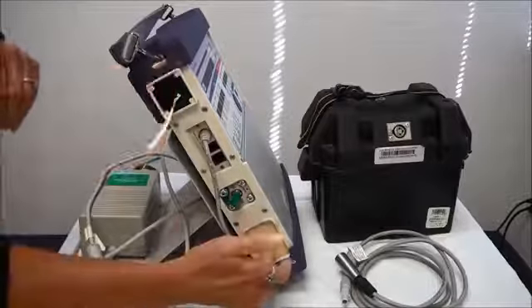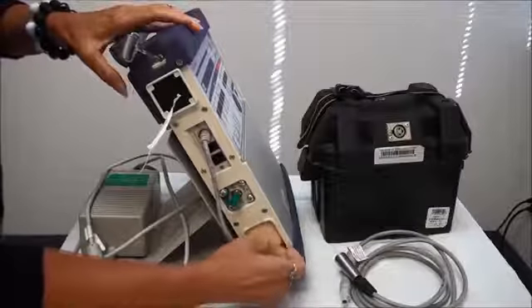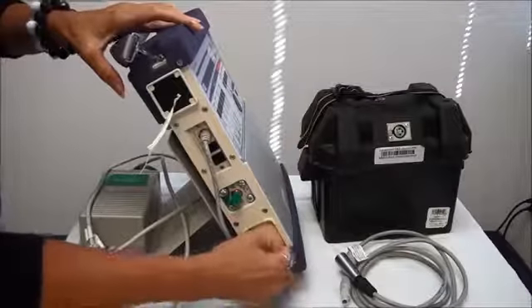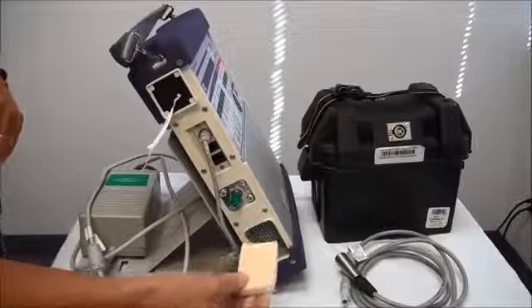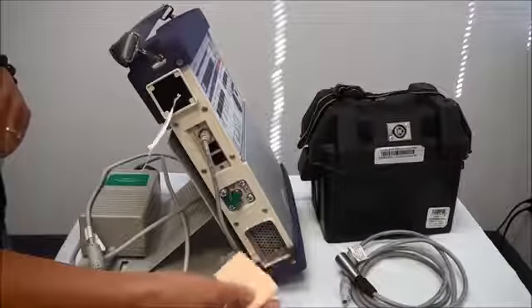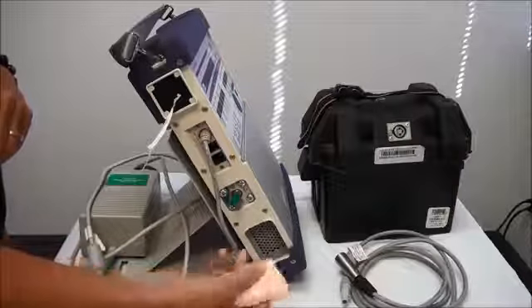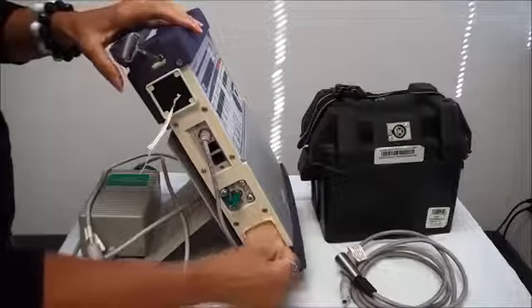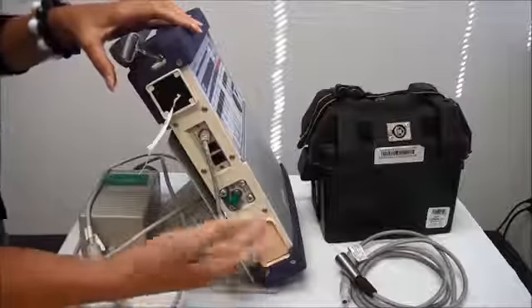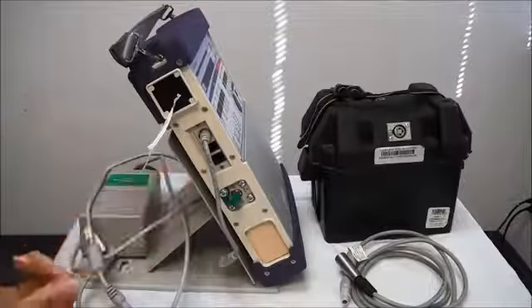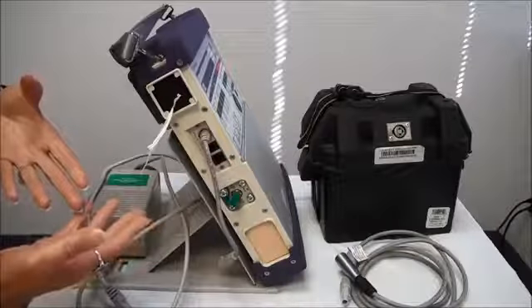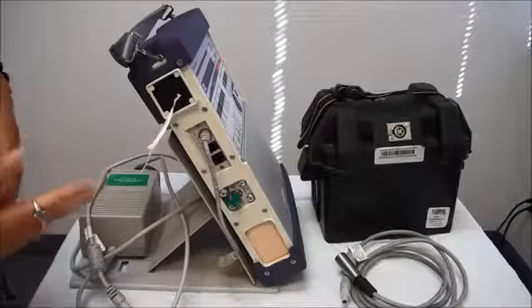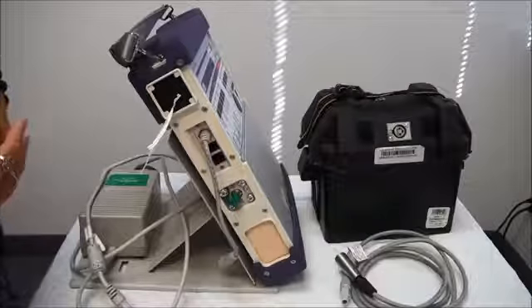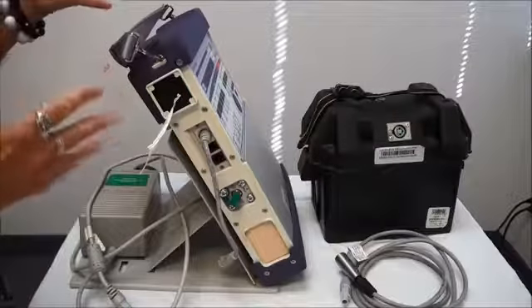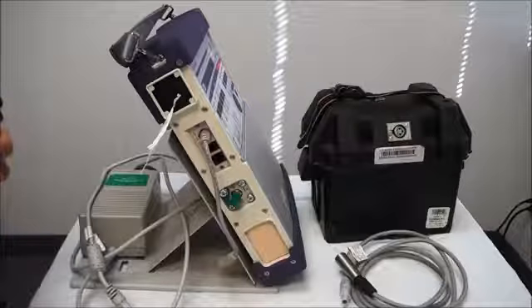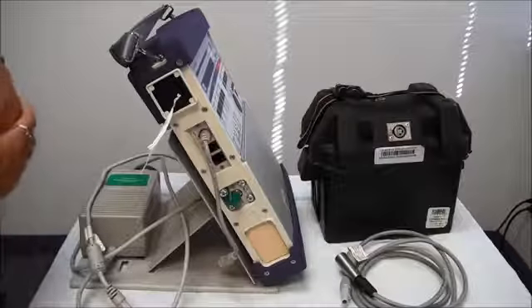Now I'm going to skip down to the bottom. There's another filter down here. There's no cover over this filter. It's a foam filter, and it just needs to come out again weekly when it looks dusty or dirty. Rinse it out with tap water, squeeze it out and let it air dry, and then pop it back in. Now in most cases you'll have more than one of these filters, so you can take the dirty ones out and put clean ones in immediately and do your cleaning, because you do not want to run the ventilator without the filters, because then you're going to get dust and particles that'll go inside the ventilator, and it can affect the ventilator and cause it to not work anymore.